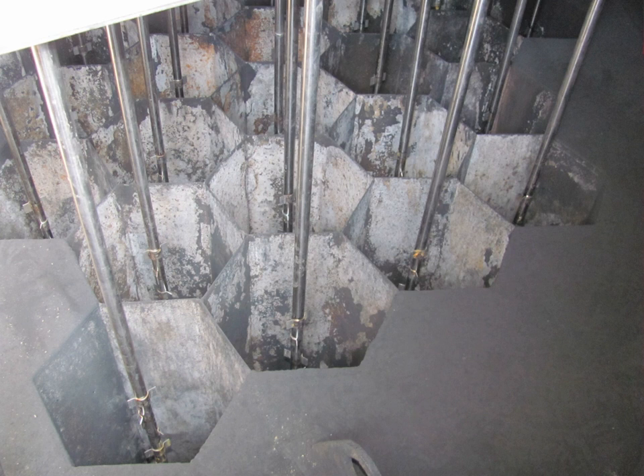The preferred and most modern type of WESP is a downflow tubular design. This design allows the collected moisture and particulate to form a moving slurry that helps to keep the collection surfaces clean. Plate style and upflow design WESPs are very unreliable and should not be used in applications where particulate is sticky in nature.